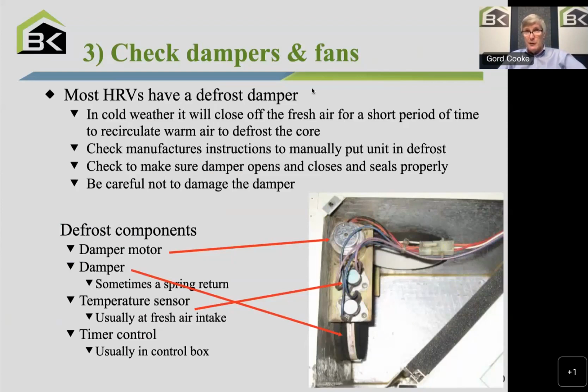Now, you need to be careful. I don't want you to manipulate this by hand, or if you do, very slowly. You don't want to force this damper. Some dampers you can move manually, some dampers you can't. So don't overplay that. What you'd really want to do is turn the unit back on once it's clean and watch to see if it's working correctly.